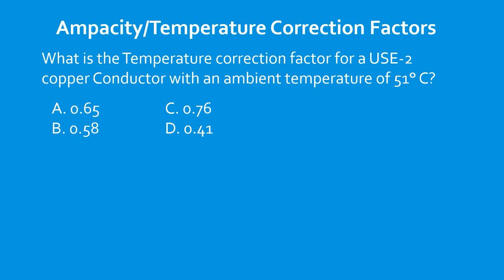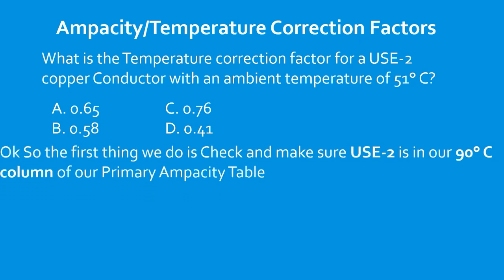Question: What is the temperature correction factor for a USE-2 copper conductor with an ambient temperature of 51°C? Confirm USE-2 is in the 90°C column — it is. Flip to the temperature adjustment factor table. This is in Celsius, so start on the left-hand side, come down to 51°C, then come all the way over to the 90°C column. We find a correction factor of 0.76.